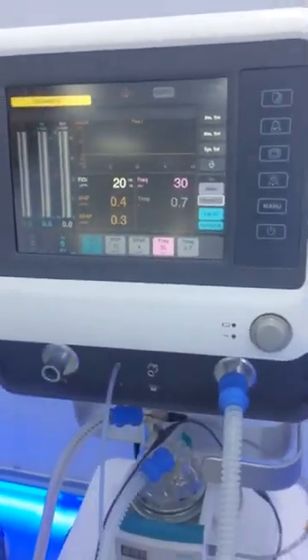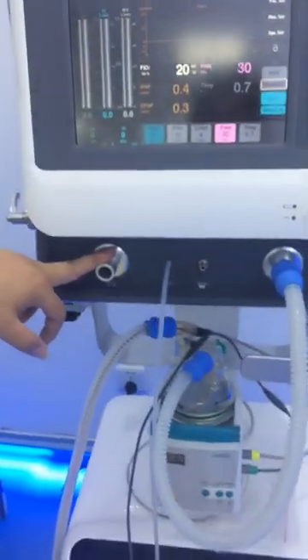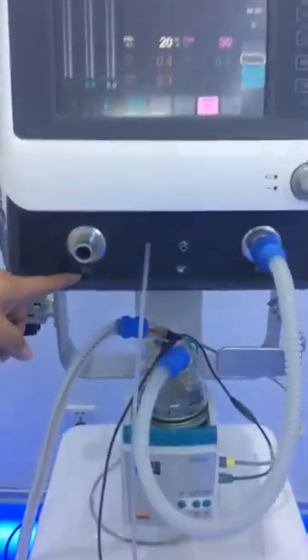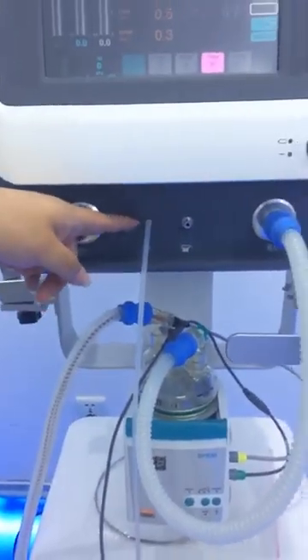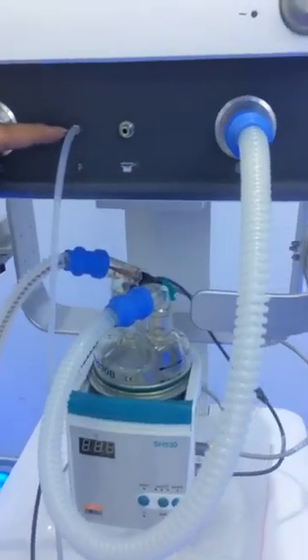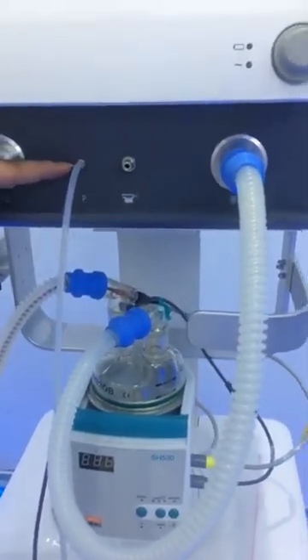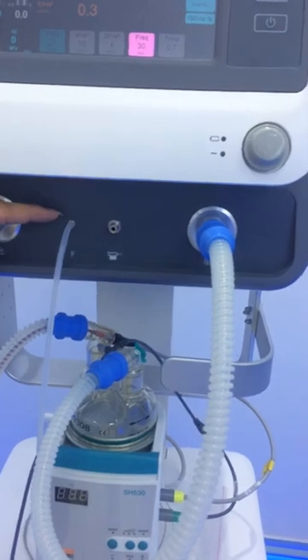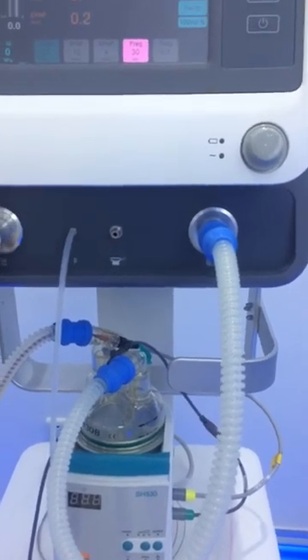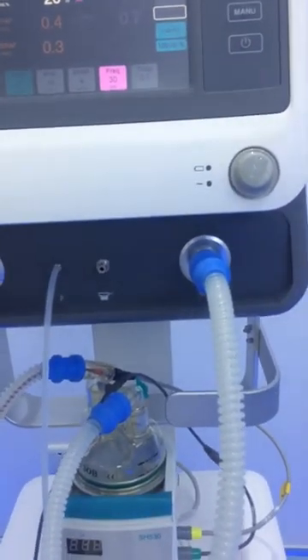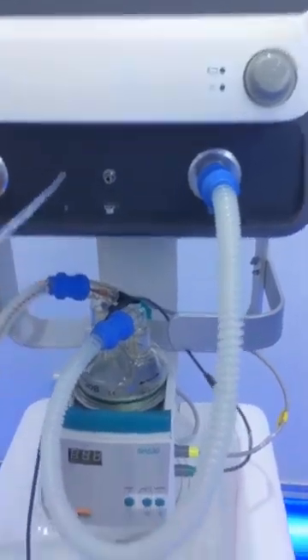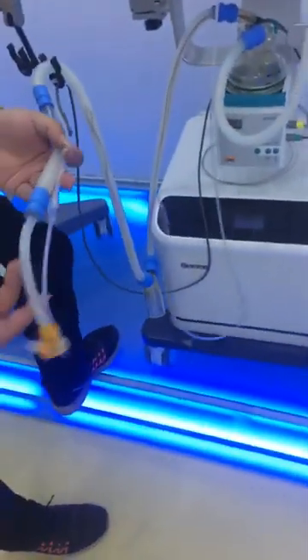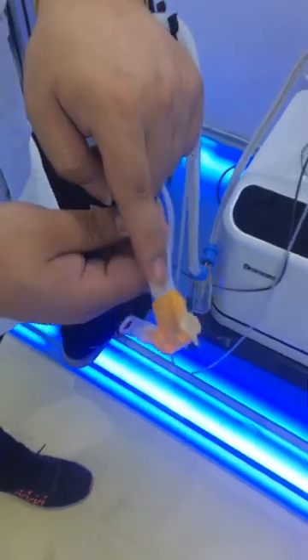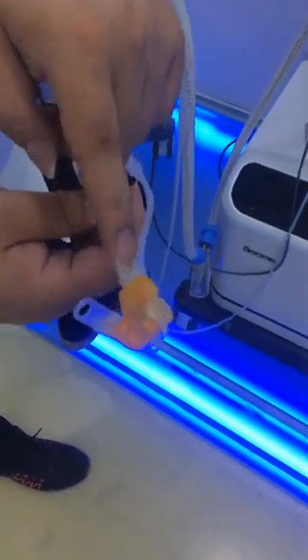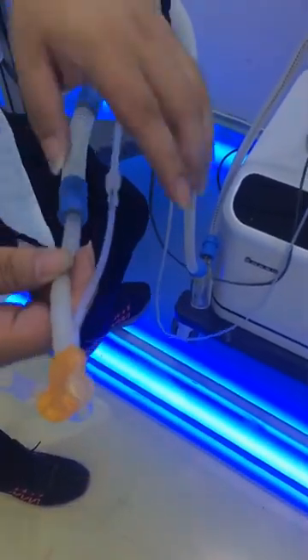Then let's see downstairs for the ports. Here we have 4 ports in total. The first one is for the expiration port. And in the middle, we have a pressure tube. You must remember to connect this pressure tube, because this tube is for monitoring the patient and the pressure. You can see the other side is connected to the nasal tube, so we can test very accurately from the baby's end.